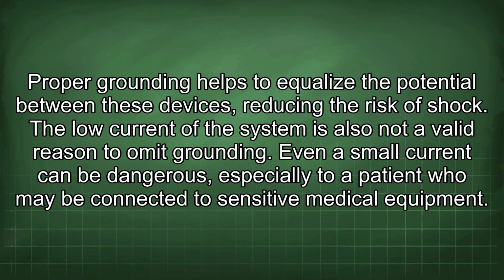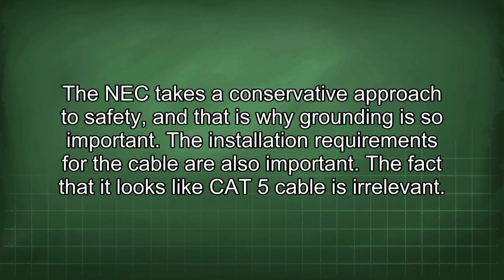The low current of the system is also not a valid reason to omit grounding. Even a small current can be dangerous, especially to a patient who may be connected to sensitive medical equipment. The NEC takes a conservative approach to safety, and that is why grounding is so important. The installation requirements for the cable are also important. The fact that it looks like CAT5 cable is irrelevant.